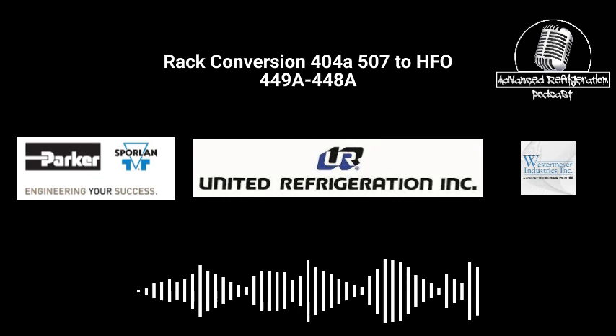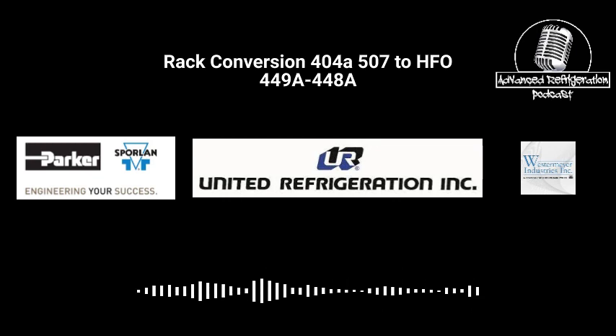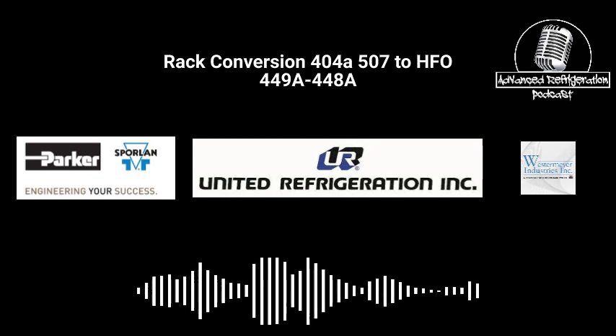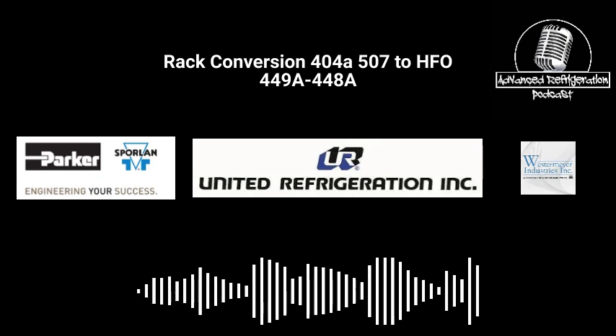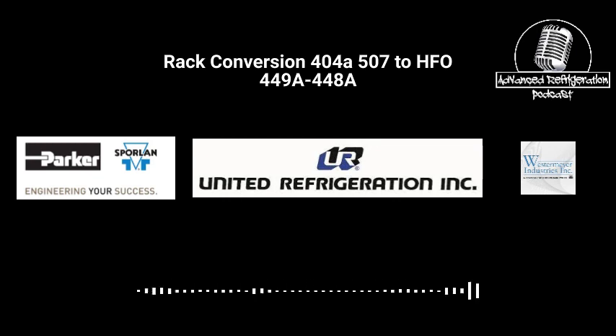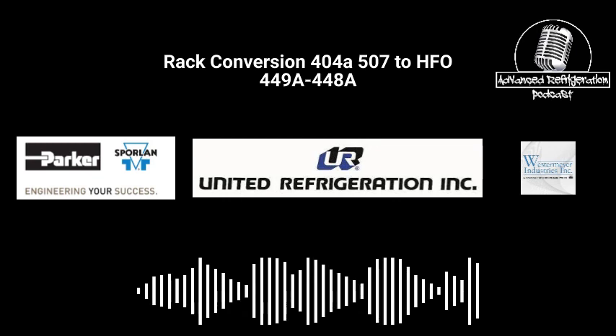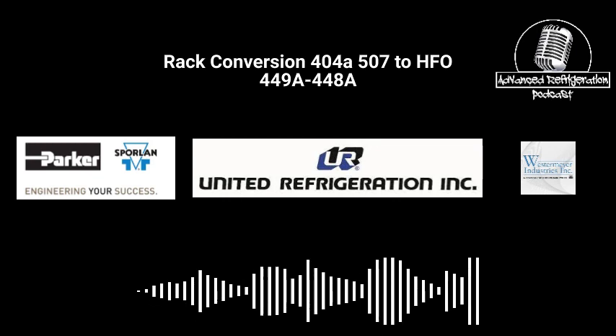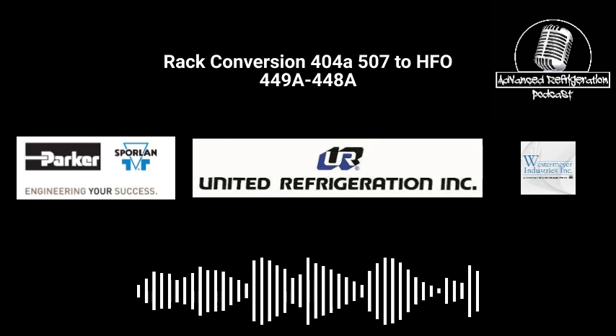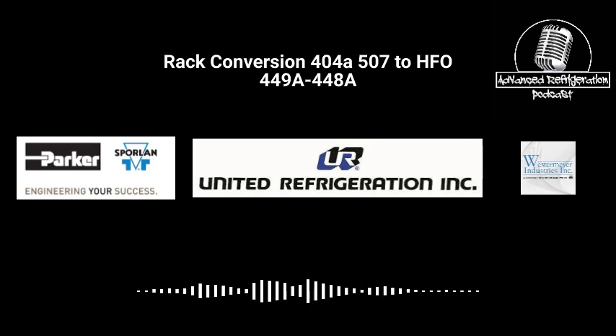It's going to be more cost up front, a little more cost up front, but I'll tell you what, to do 2 or 3 ball valves here, 2 or 3 ball valves there, it's going to be way more expensive than just doing them all in one shot. So I'm a big proponent of getting those ball valves out. If they're leaking at all, if there's any signs of them leaking, then I'm going to go through and gut them all. All the high side ball valves are coming out. At a bare minimum, the drop leg and discharge ball valves are getting changed.